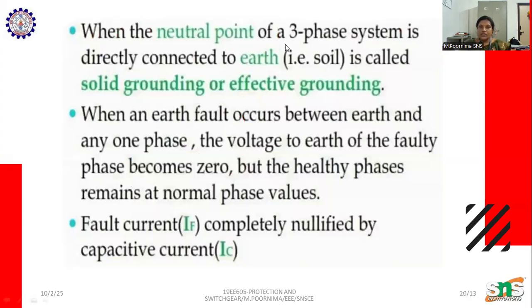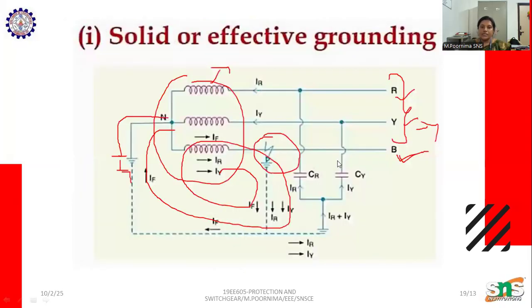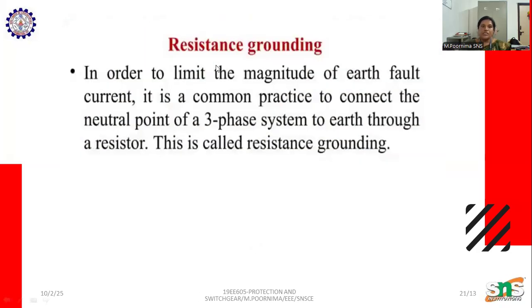When a three-phase system is directly connected to the earth, it is called solid grounding or effective grounding. When an earth fault occurs between the earth and any one phase, the voltage to earth of the faulty phase becomes zero, but the healthy phases remain at the normal phase value, as already discussed. The fault current is completely nullified by the capacitive current IC. Here we can see the capacitive current IC.